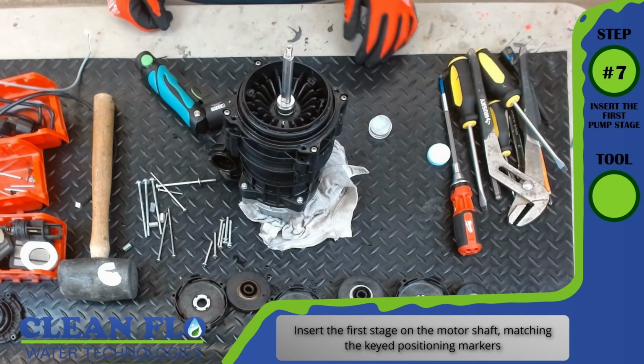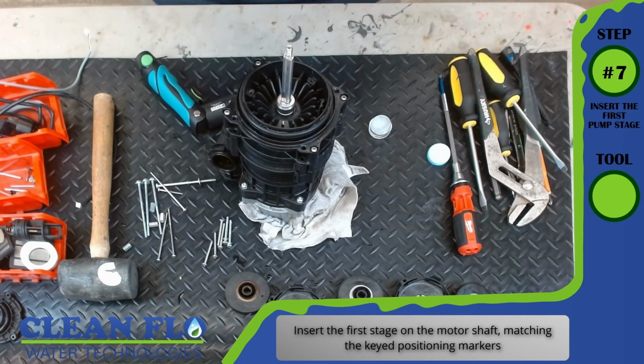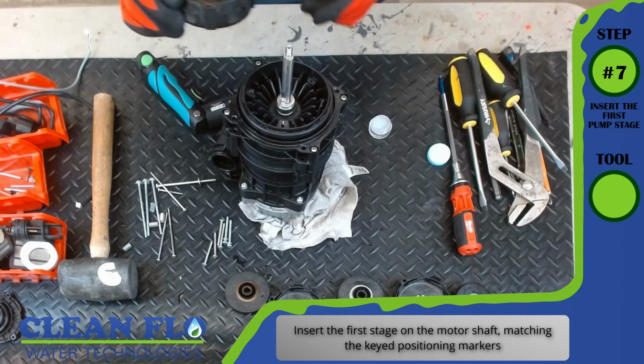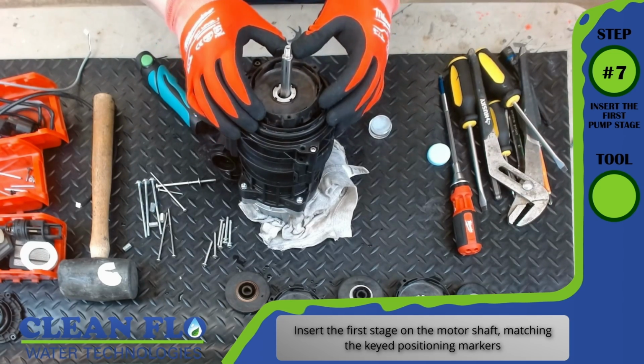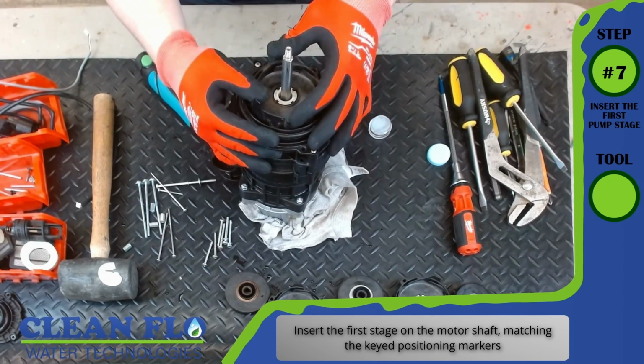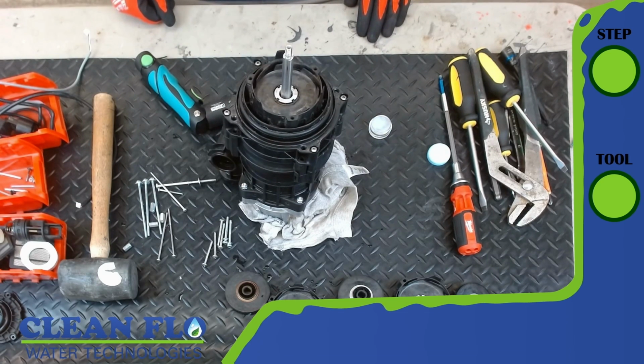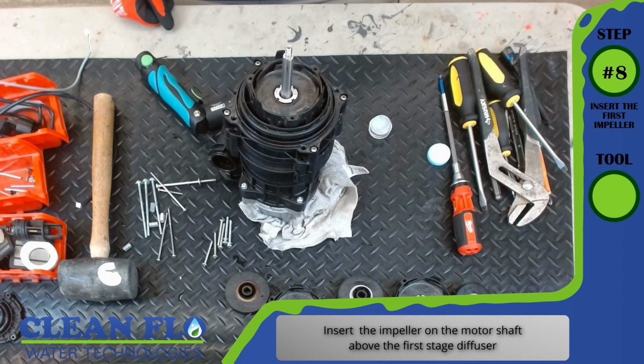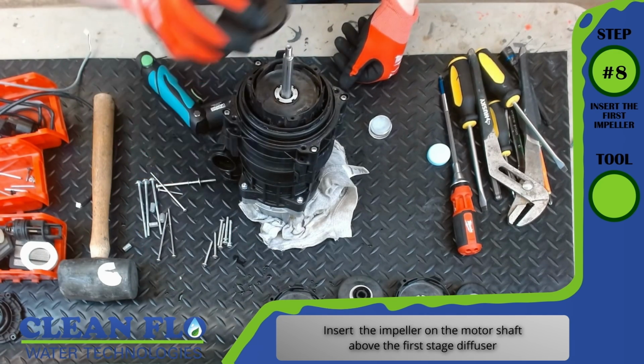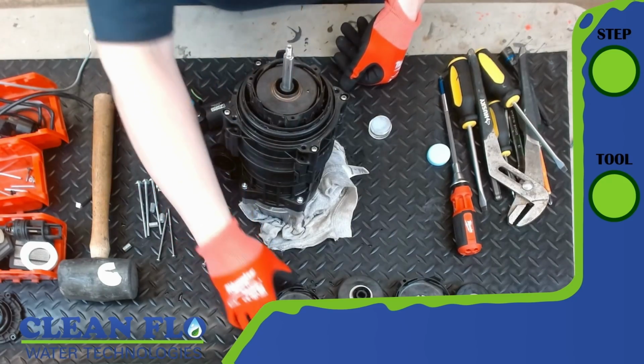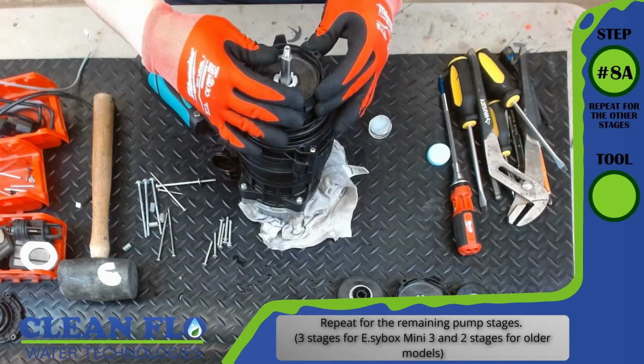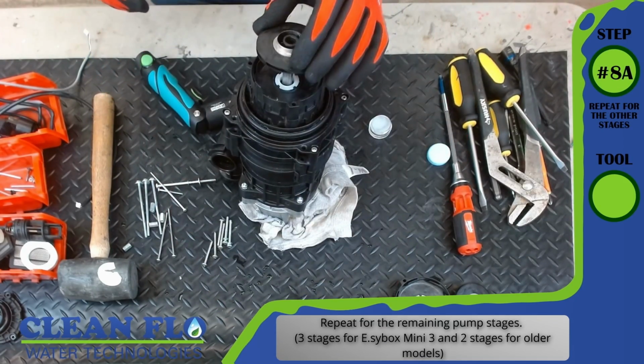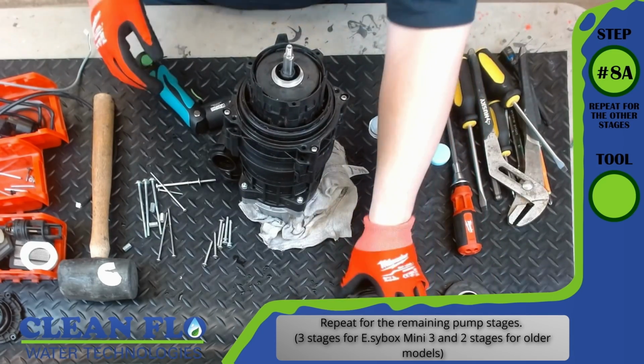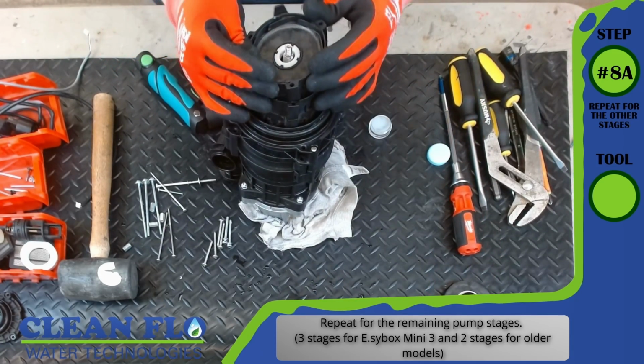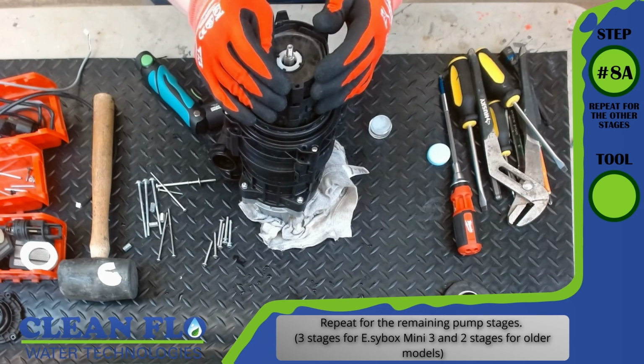Step number 7, insert the first pump stage. Insert the first pump stage on the motor shaft, matching the keyed positioning markers. Now these components are called the diffusers. Step number 8, insert the first impeller. No tool required. Insert the impeller on the motor shaft above the first stage diffuser. Step 8A, repeat for the other stages. Repeat the remaining pump stages. 3 stages for Esybox Mini 3 and 2 stages for the older models.